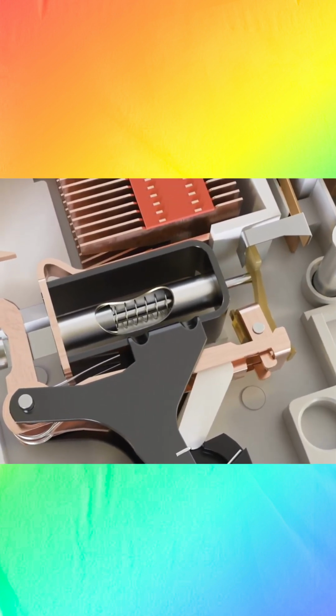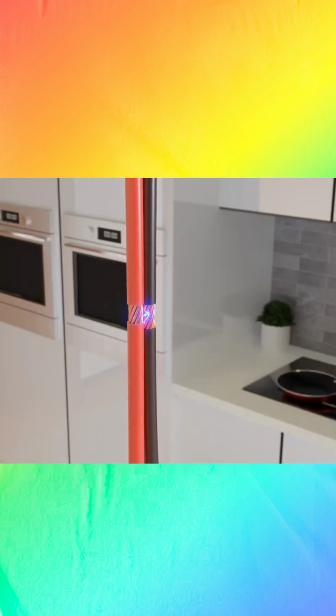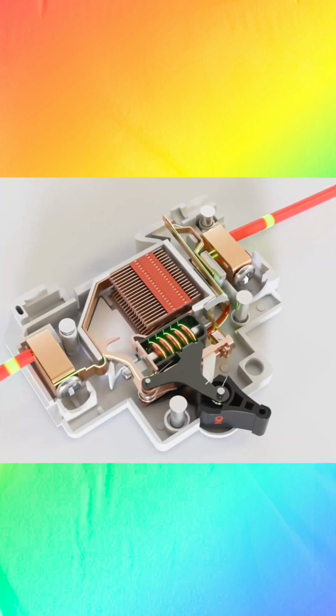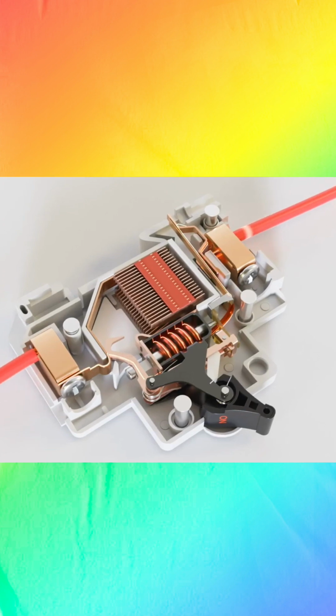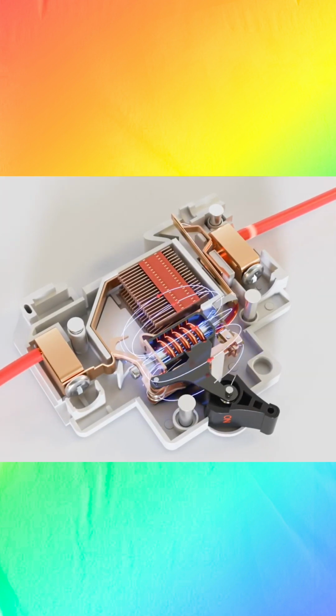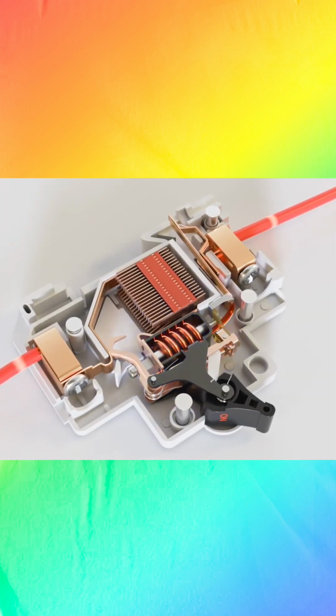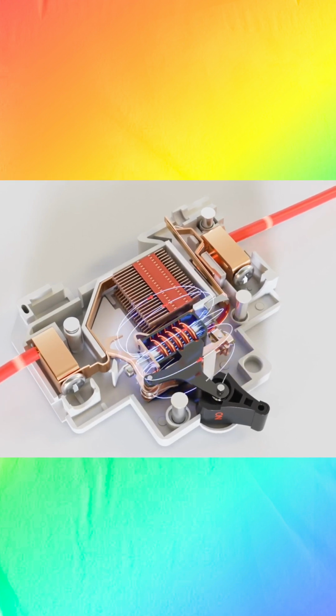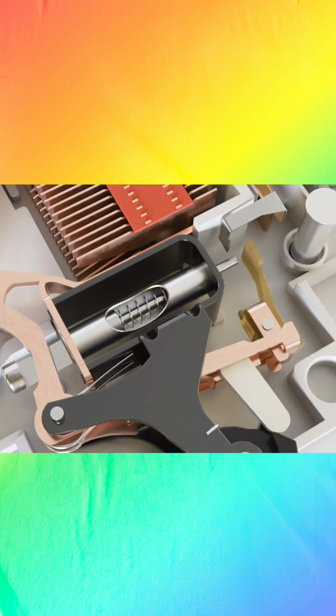But in case of a short circuit, the value of current can rise to 50 or even 100 times its normal value. As a result, a much stronger magnetic field is created, which applies a significant amount of force on the cylinder. Due to this force, the cylinder moves and triggers the operating mechanism, causing it to immediately cut off the circuit. But it is not over yet.